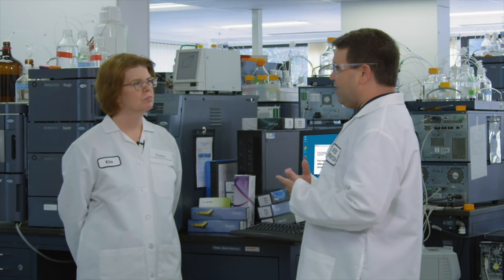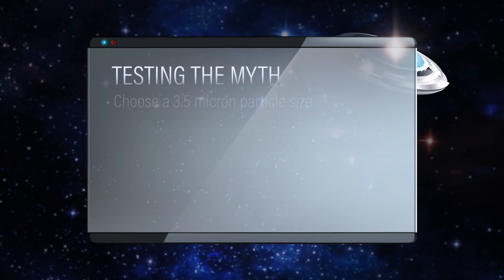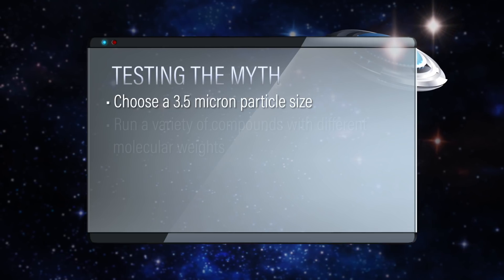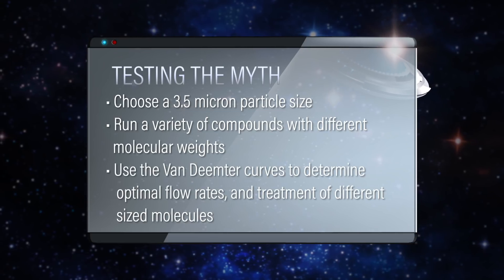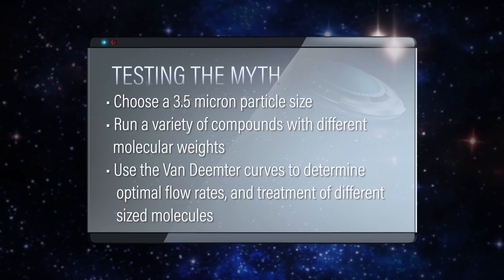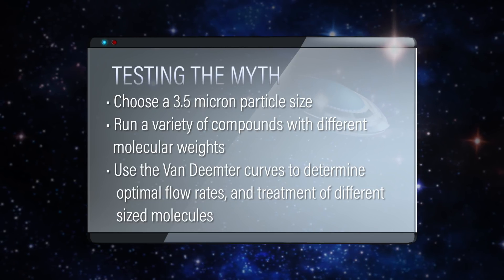I think it might be really important to take a look at some van Deemter curves, because with small molecules you can run pretty fast — up to maybe 800 microliters a minute without losing a lot of efficiency. It'd be nice to know if that holds true for larger molecules. So we can pick a 3.5 micron particle size and run a variety of compounds with different molecular weights, from small to larger, and see what those van Deemter curves look like to find the optimal flow rates.